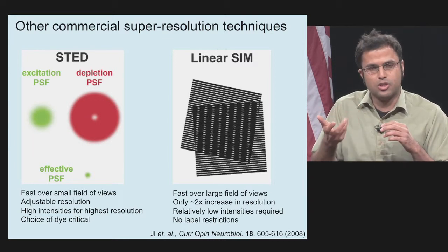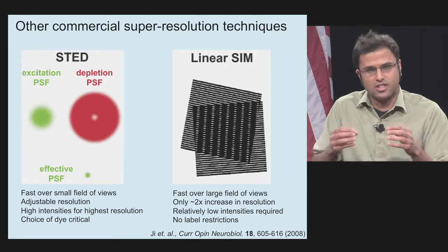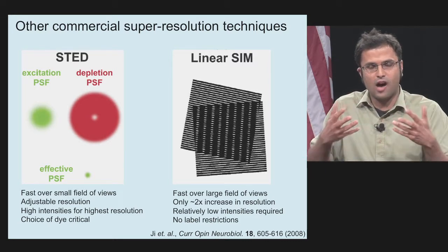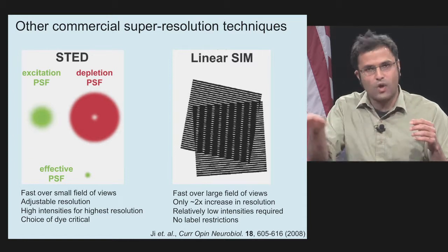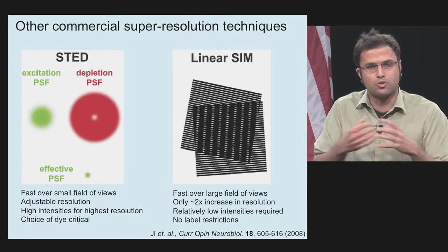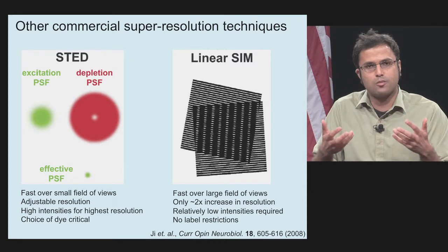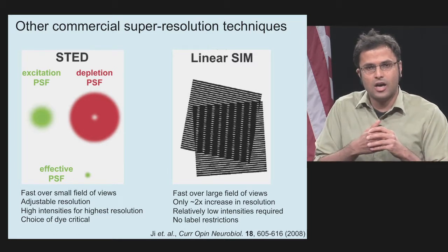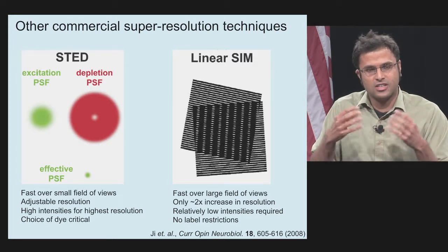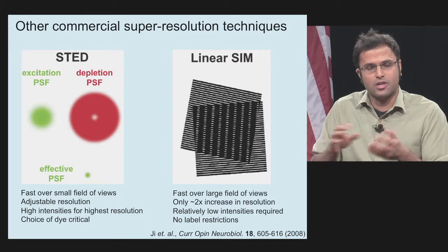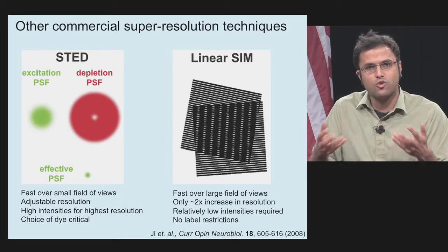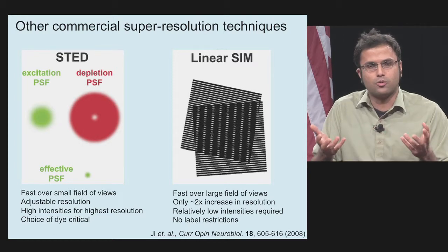Stimulated emission depletion microscopy, or STED, forces all fluorescence except for a very narrow sub-diffractive region within the point spread function radius off, and this sub-diffractive region is rastered throughout the sample to build up a super-resolution image. STED is very fast over small fields of view and can be applied to somewhat thicker samples like mouse brains, but dye choice is critical and you need very high intensities for the highest resolution. Structured illumination microscopy is far more gentle on the sample; in its linear form it only affords a factor-of-two resolution gain, but there are no label restrictions.